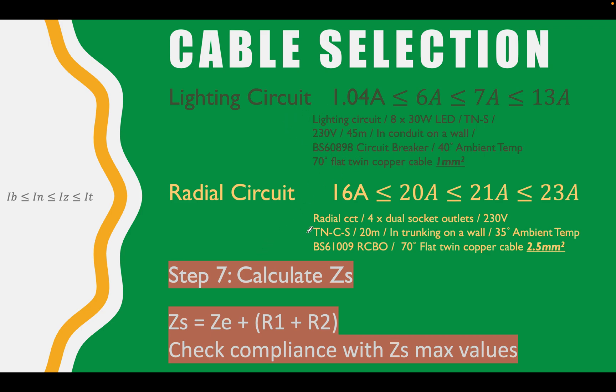So you can see on here we've got lighting circuit, radial circuit, and we've gone through this formula, which is this one, and we've satisfied each part of it so far and we've selected our cable sizes, 1mm and 2.5mm. We previously calculated our R1, R2 value, so we're going to bring that into this step now and add it to our ZE to give us our ZS value. And then we're going to check compliance with the ZS maximum values. We're going to look at them in the on-site guide and in BS7671.